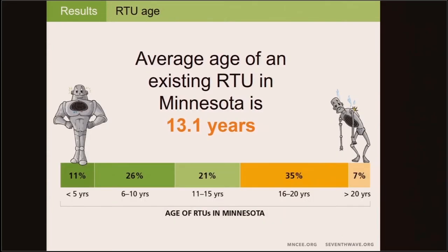The age of RTUs also has an impact on energy performance, because newer RTUs may have higher efficiencies and system performance tends to degrade over time. The average age of an existing RTU in Minnesota is 13.1 years. Newer RTUs, or those that are less than 5 years old, comprise 11% of existing RTUs. Also, only 7% of existing RTUs are older than the Minnesota Technical Reference Manual's value of 20 years for estimated useful life.